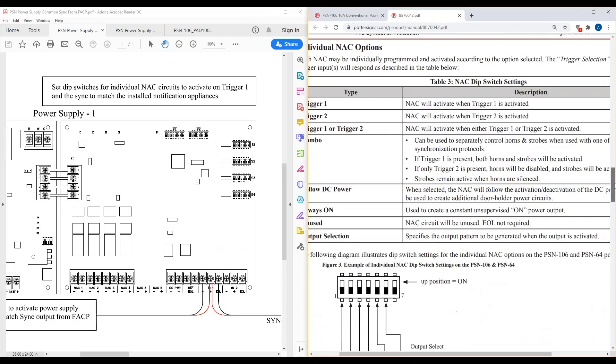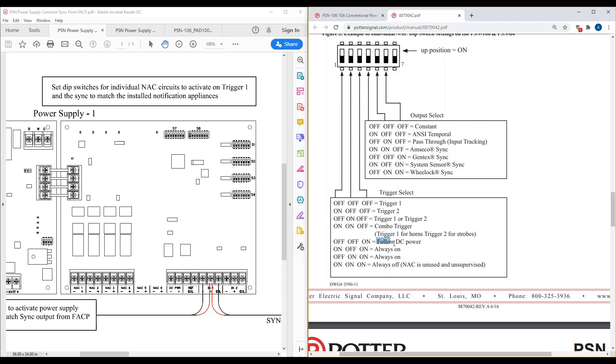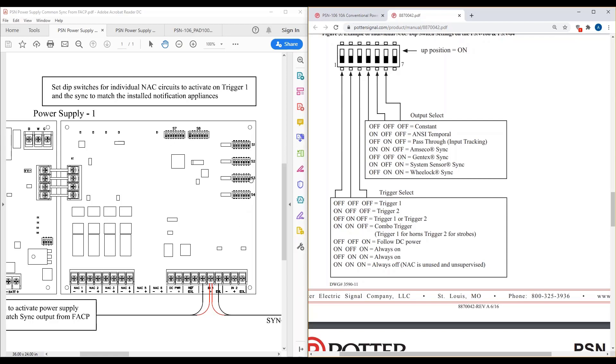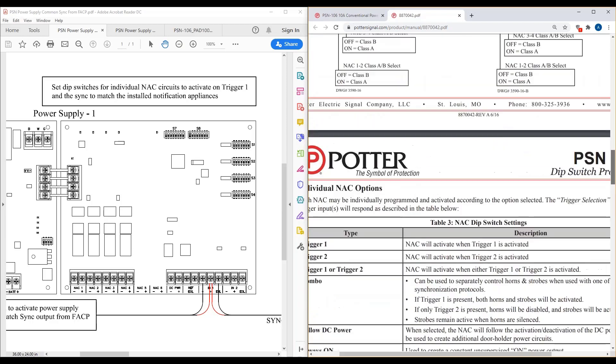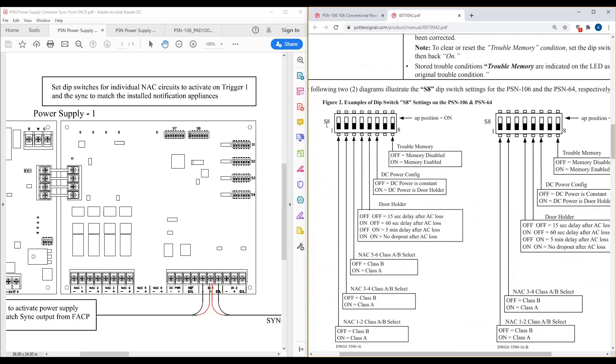So what I was referring to is the individual NAC options of the triggers, as you see here. And then the one that confuses people is when they read follow DC power, they don't really understand what that is. The DC power is configured by dip switch bank S8. So if you look at the drawing here on the left hand side, you have dip switch bank S7, then S8, and then your individual NAC dip switch banks. So if I scroll up here, that's dip switch bank S8 right here. This is where you're going to see the DC power config. That's where you can choose whether it's constant power or door holder power.